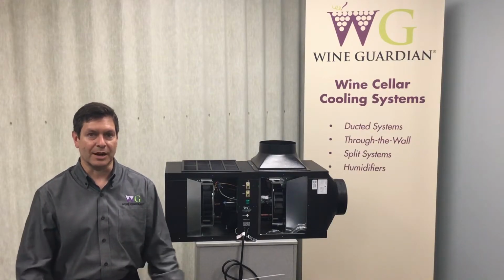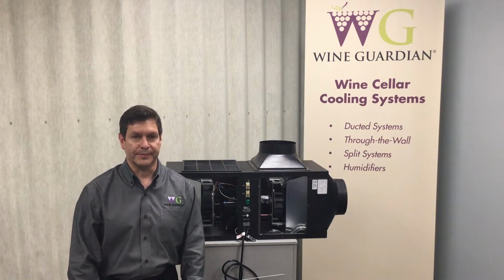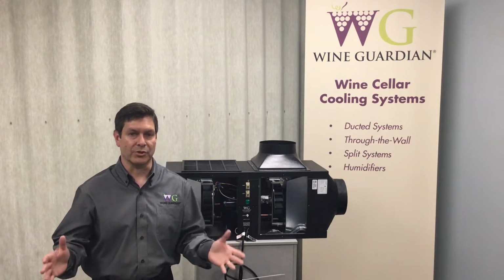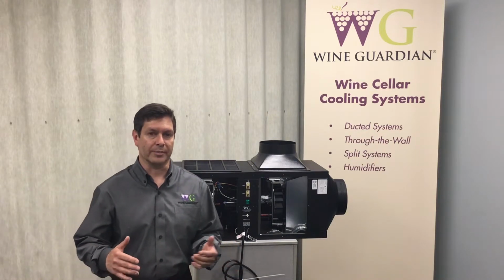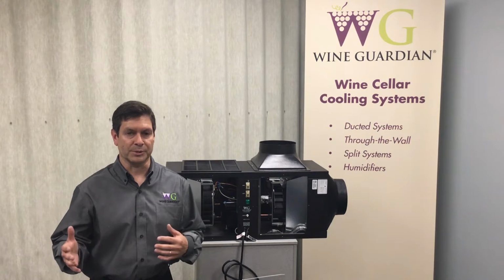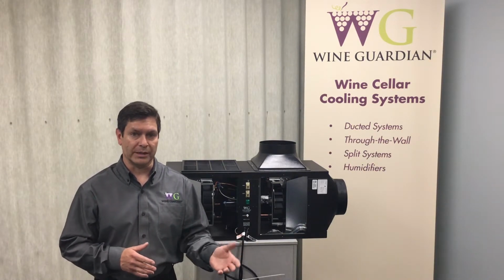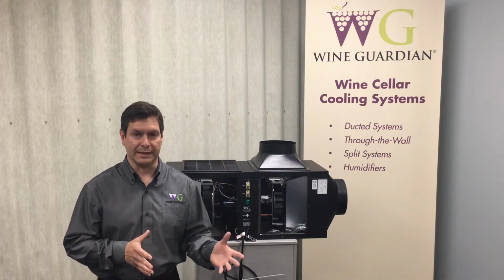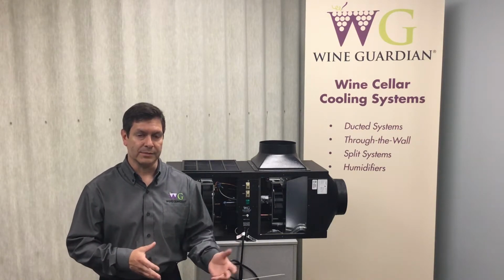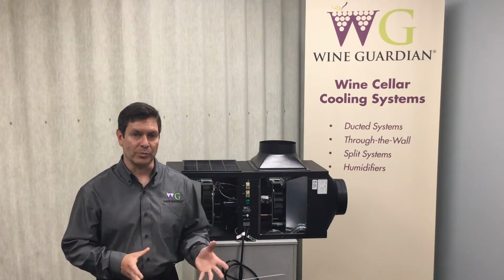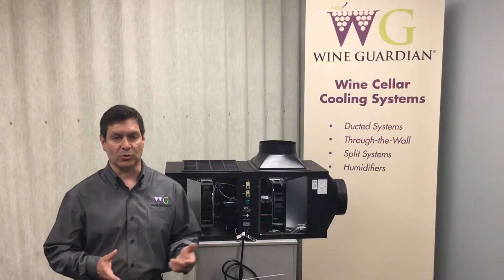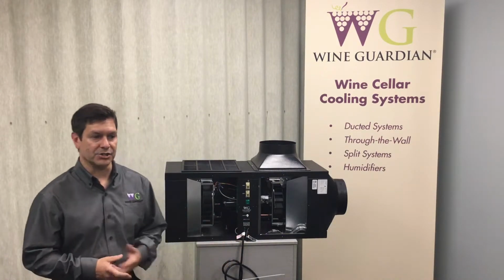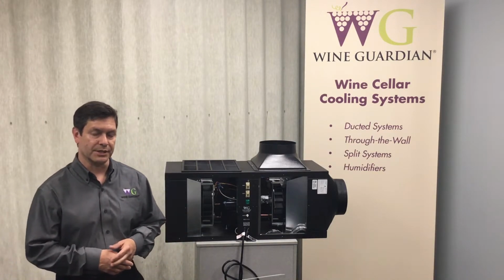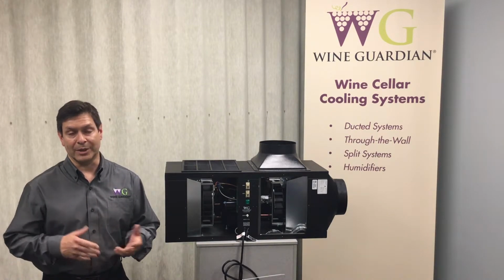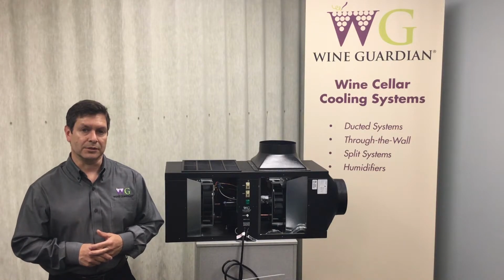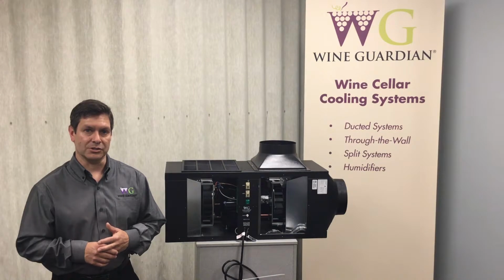The serving temperature option is another option that we have with all of our wine cellar cooling units. What the serving temperature option does is it broadens the range of control for the unit. So you'll go from a maximum of, say, 65 degrees Fahrenheit, to being able to control the space down to a low of about 42 degrees Fahrenheit. So for white wines, maybe in a small cabinet or a small wine room, you can control the temperatures down to those lower conditions. So for a serving application in a restaurant or something like that, you may have one cabinet set to 42 degrees, another set to 55 or 57, and then maybe another cabinet or room set to the low 60s. So that gives you a range of serving conditions that you can set the units up to do.